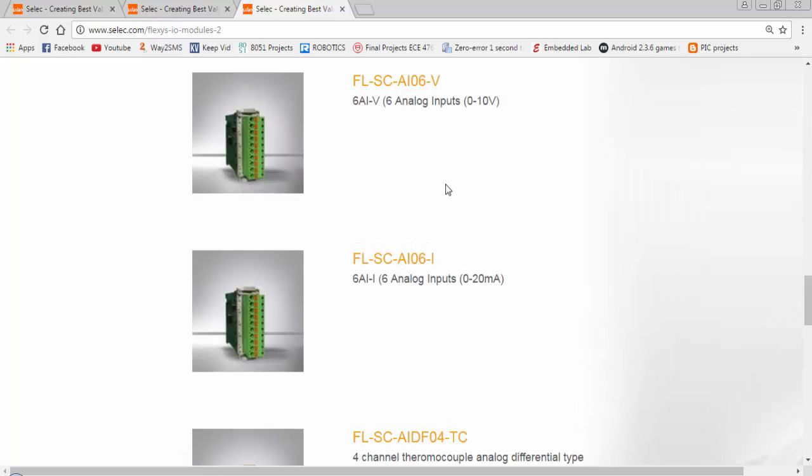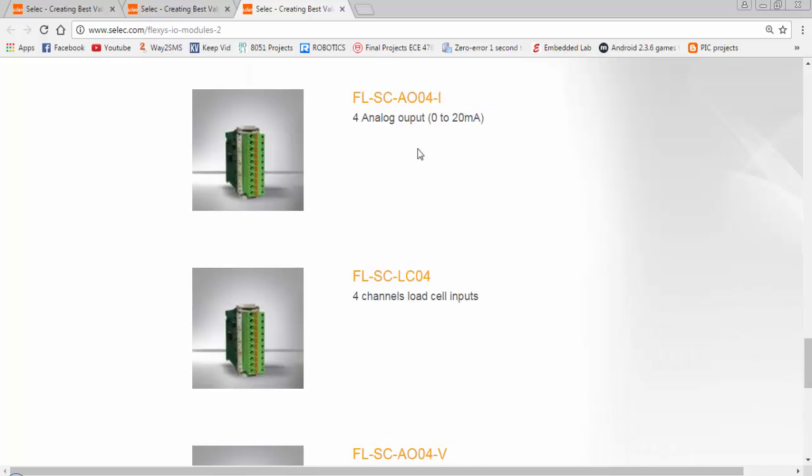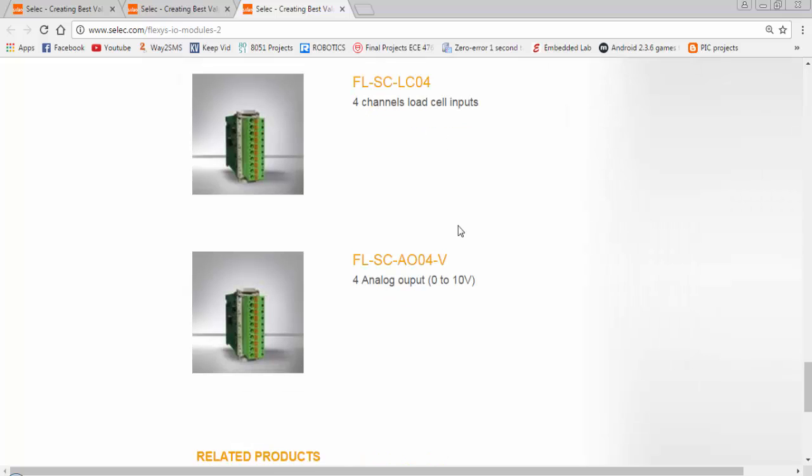To increase the analog inputs, we can either use 0 to 10 volt card or 0 to 20 milliampere card. To increase the analog output channels, we can either use a current output card from 0 to 20 milliampere or we can use analog output card for voltage 0 to 10 volt.